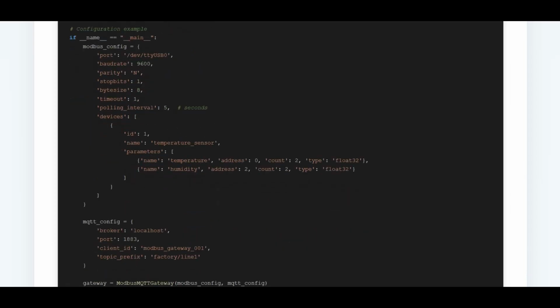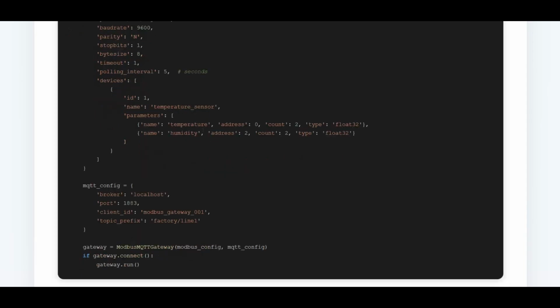And look at the configuration example here. Modbus settings define serial port, baud rate, parity, stop bits, byte size, timeout, and polling interval. Devices are defined declaratively. Each device has an ID and a name and a list of parameters. Each parameter has a name, address, register count, and type. MQTT configuration defines broker address, port, client ID, and topic prefix. At the very bottom, we instantiate the gateway, connect it, and run it.